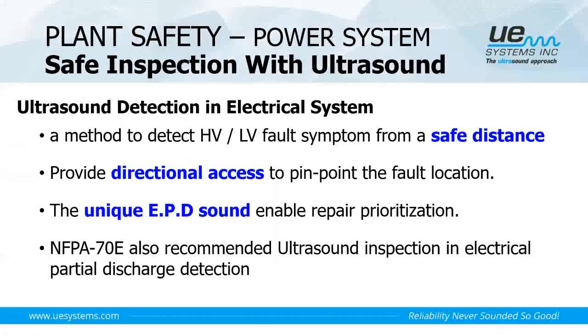So for safe inspection, ultrasound provides a safe method for electrical inspection from a safe distance. It provides directional access to pinpoint the fault location. Electrical partial discharge noise is unique, and this will enable repair prioritization. Besides, NFPA 70E also recommends ultrasound inspection in electrical partial discharge detection.